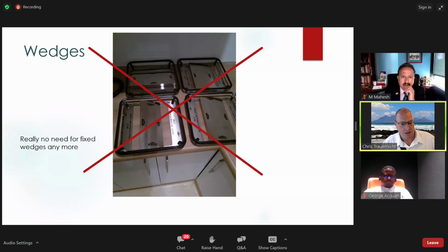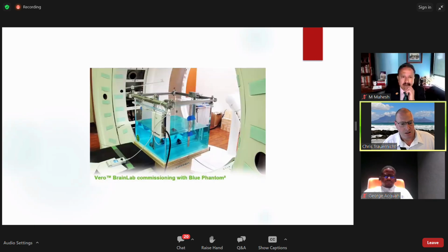When you specify a LINAC, you have to think a little bit about what additional equipment you need. You will need a water tank to commission the LINAC. There was a build here in Cape Town, a massive, top-end LINAC, and they just didn't want to spend the additional money for the water tank. So they approached our hospital at the time, can we please borrow yours? We were stupid enough to say yes, and it came back slightly worse for wear, and we had to replace it soon afterwards.